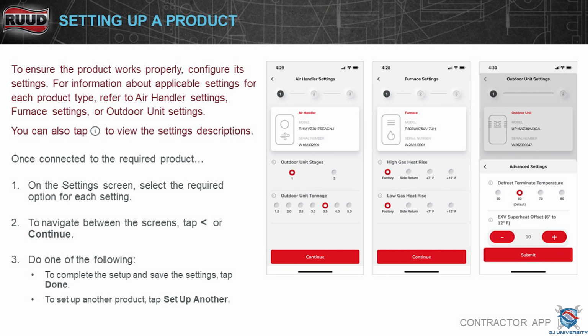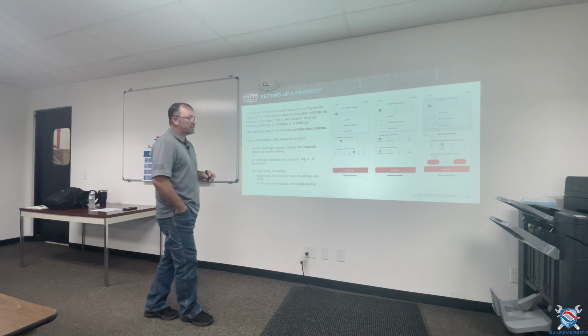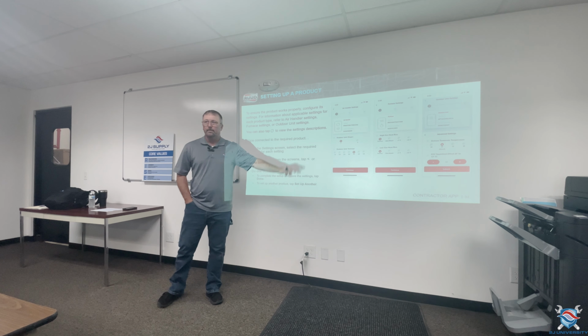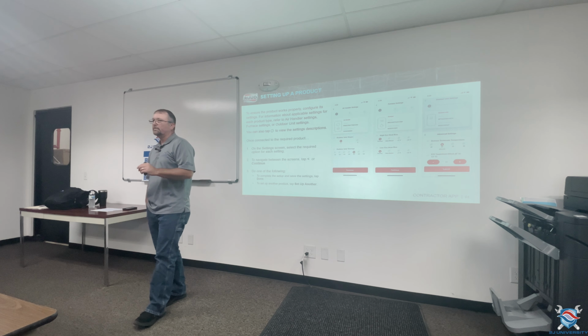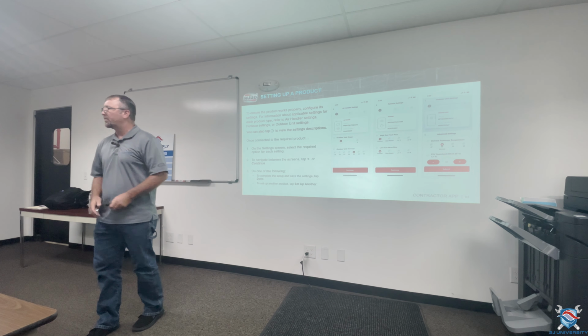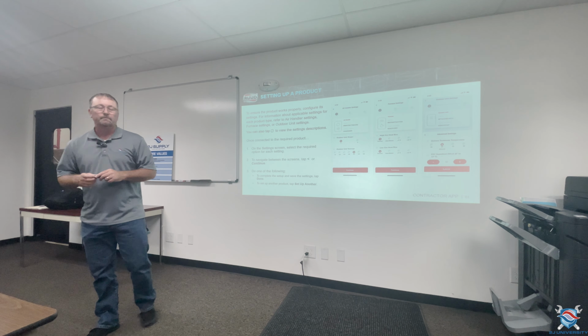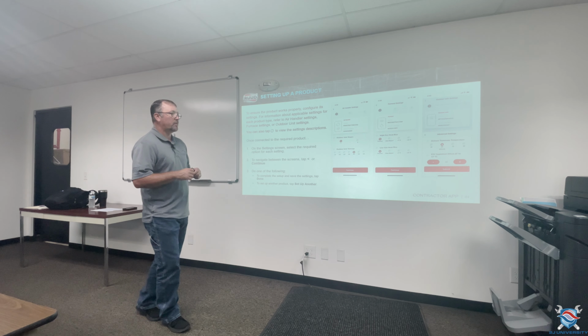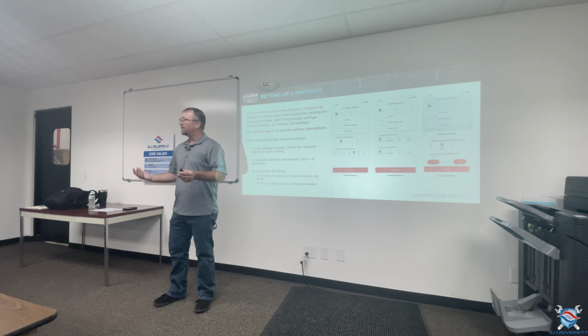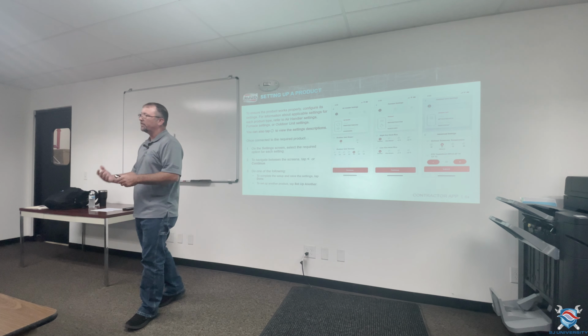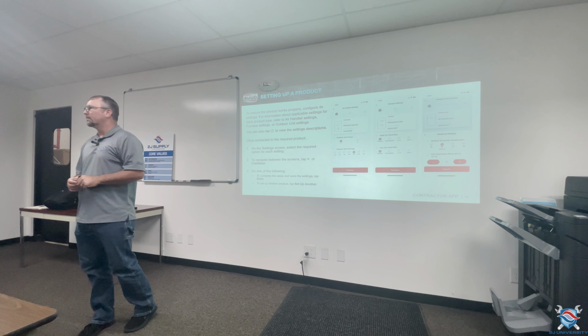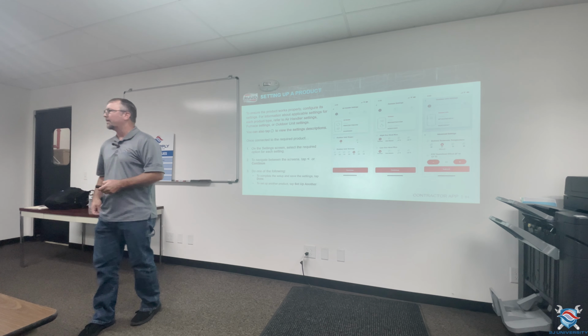Defrost termination, you can set whether you want 50, 60, 70, 80 degrees. Another feature that is put in this, if it has an EXV, you can tune your superheat on your EXV as well. I don't know why you would want to do that, but there may be a situation that you run into that you want to look at a different superheat than what it's actually giving you.